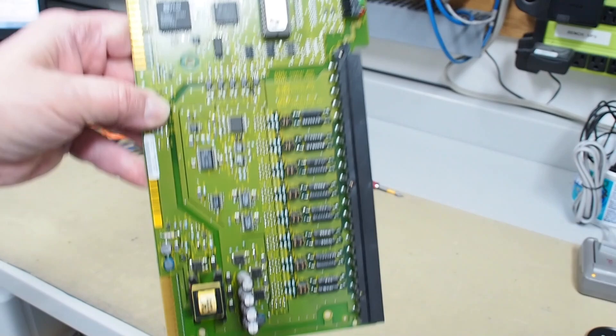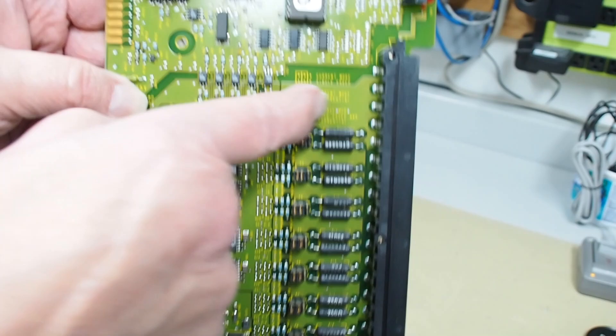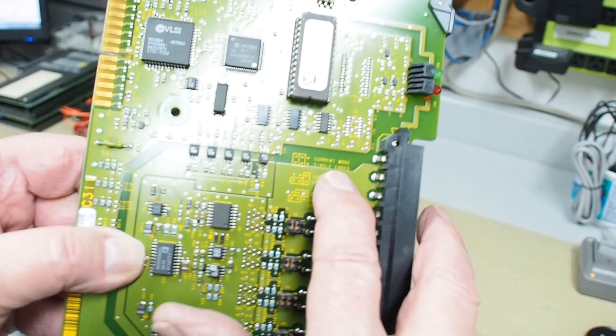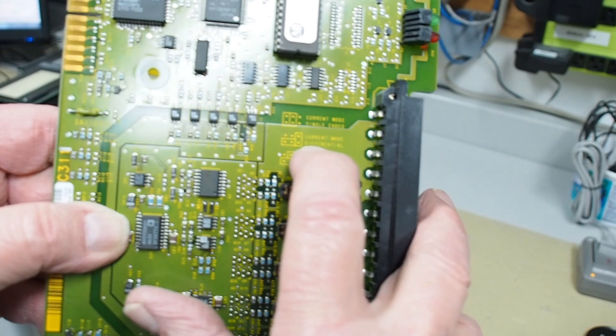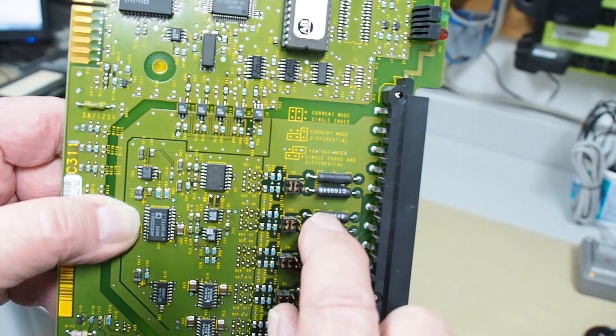You can set this card up in three basic different configurations. You take out your four screws, move your cover over, there's the inside. Here's the inside of the card. Right here is a diagram that shows what these jumpers do. This is how you set what you want your card to be. Currently, with the two jumpers straight up and down, it is in current mode, single ended. You can also have current mode differential, or, down here at the bottom, where you've got one this way and one that way, which is what we're going to change it to, is voltage mode, single ended and differential.